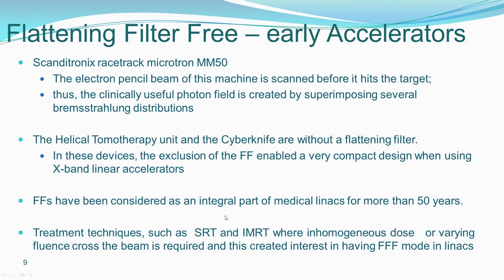Flattening filters had been considered an integral part of medical linacs for 50 years. In those days we wanted uniform fluence. But when SRS and IMRT came in, people were looking at inhomogeneous dose distributions and non-uniform fluence. Then it made sense to ask: why make a non-uniform beam uniform and then make it non-uniform again? Rather, use the non-uniform fluence directly for radiation therapy. And so the Triple F mode started becoming part of the linear accelerator.